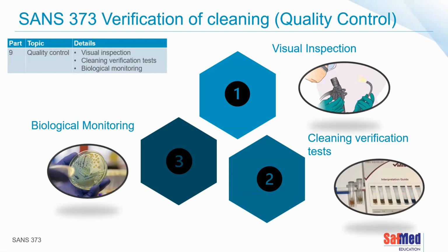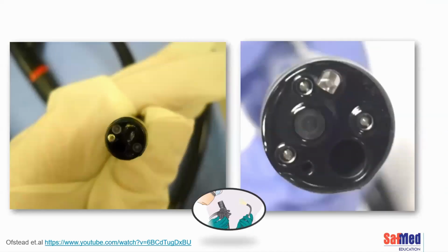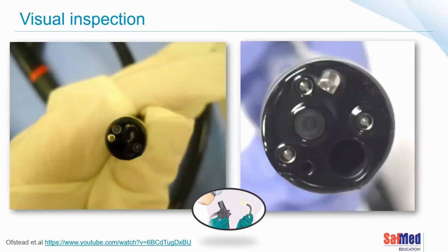Let's look at visual inspection and cleaning verification tests. A lot of guidelines internationally, and now our guideline as well, say that when doing visual inspection, we can only inspect the exterior of the scope. Aside from looking for damage—patients bite them, scopes get damaged, you've probably seen that even better than I have—the scope is dark, it's black, and it's not always easy to see the contaminants. So guidelines call for using lighted magnification so you can see better, because you can't see clearly just with the naked eye. And then, of course, there's the point that we can't see down the lumens.